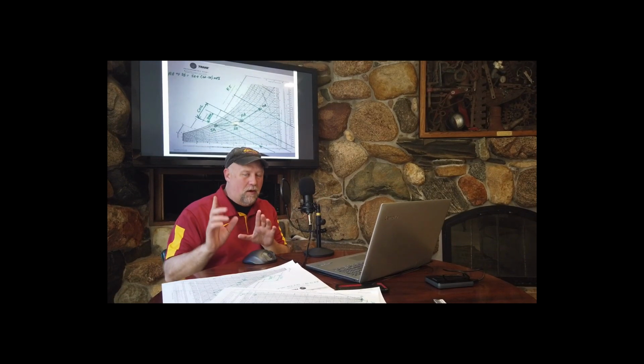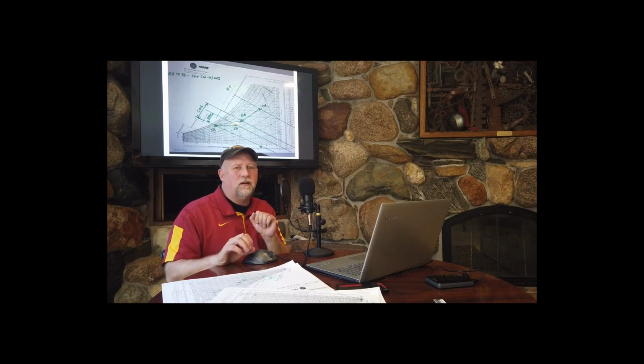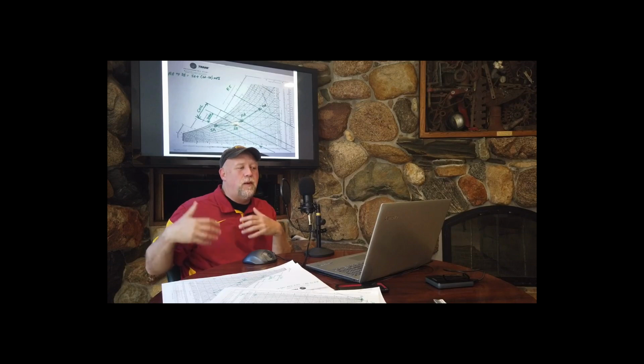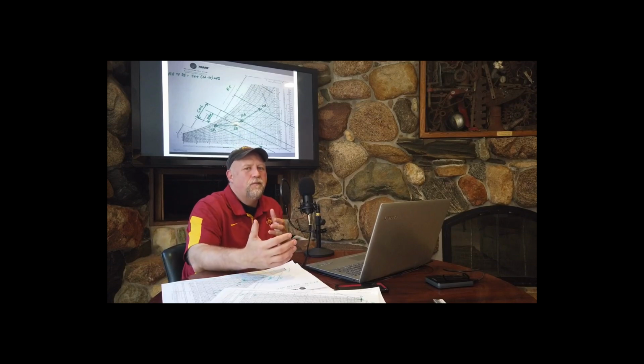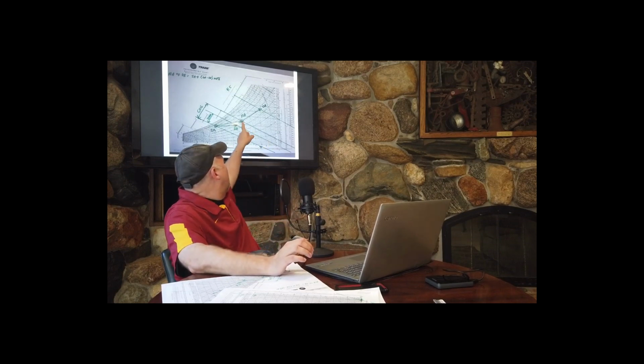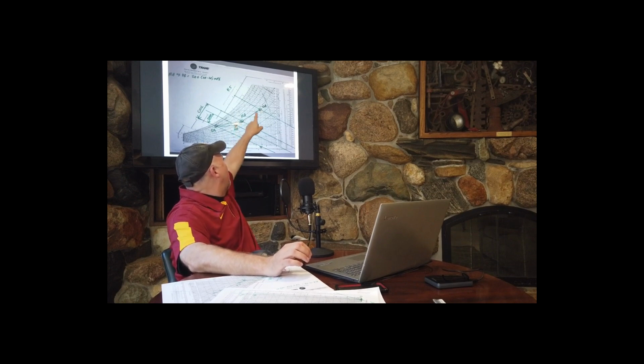So we mix that outside air that we're bringing in, ventilation on purpose, at the air handler. We're exhausting some of the room air. And what happens is as we bring that in and mix it together, that mixed air gets warmer and more moist. We plot that right here. The mixed air has to be somewhere in between return air and outside air, somewhere on this line. It has to be. Can't be anywhere else.